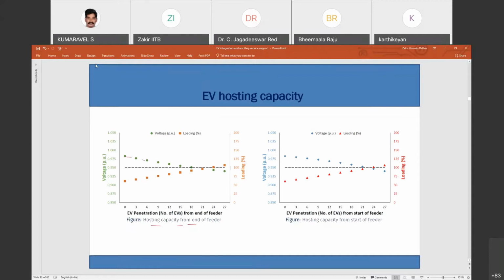The voltage goes down as EV penetration increases, as expected, and the loading on this y-axis is increasing again as expected. You can see the bottleneck: if you take 0.95 as the minimum voltage level, the bottleneck is reached here because voltage hits the minimum allowed limit. Of course we can change it; in this particular case we took 0.95. So you cannot go beyond this much electric vehicle penetration.